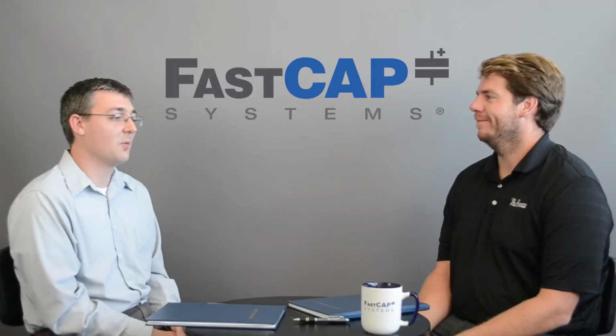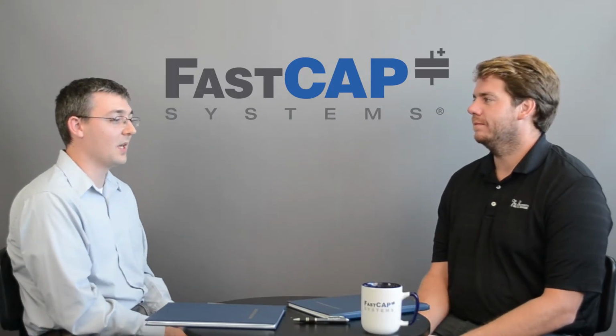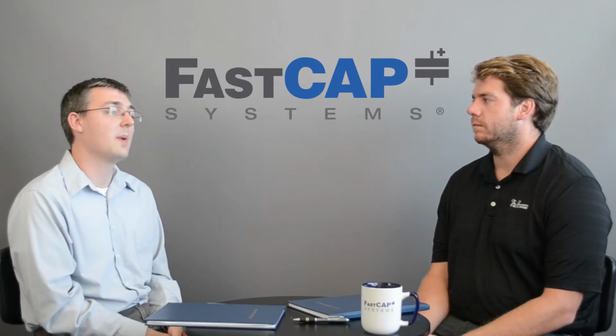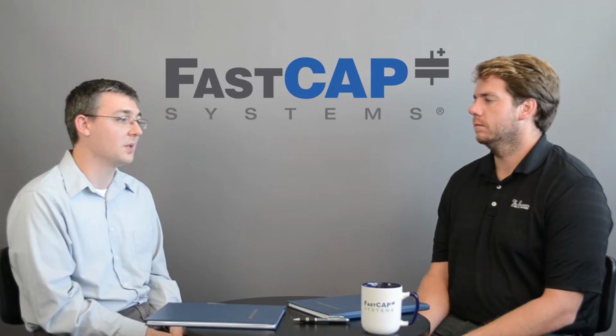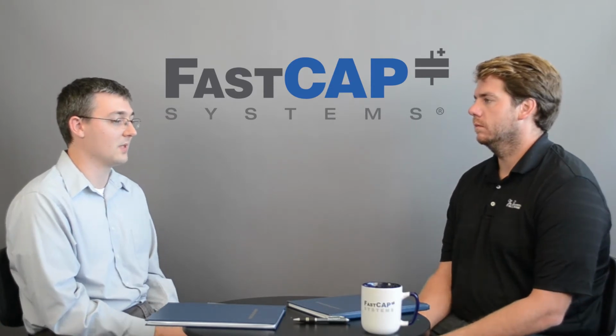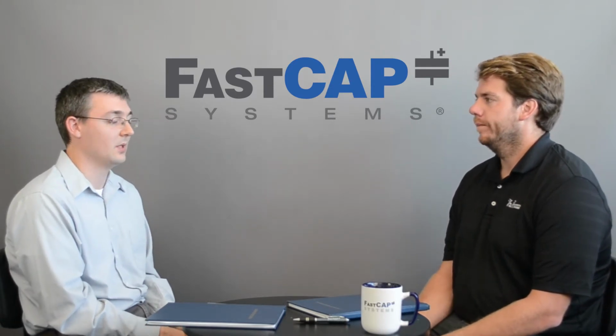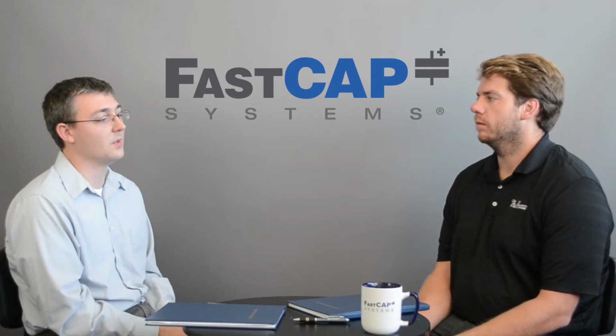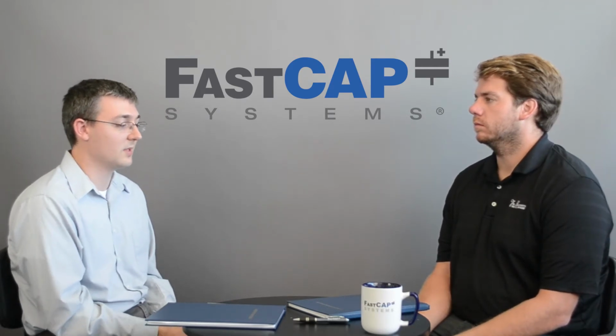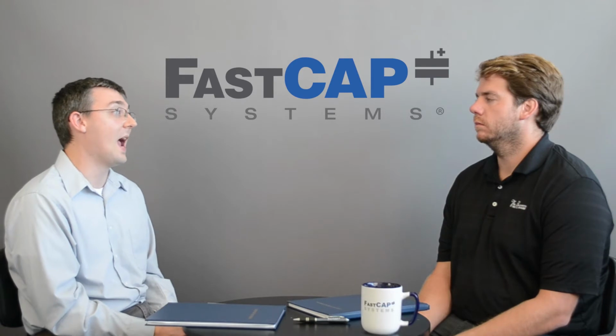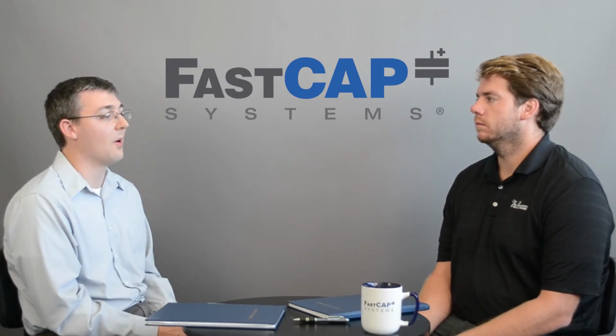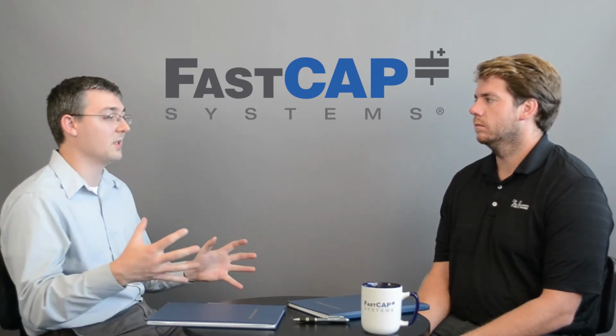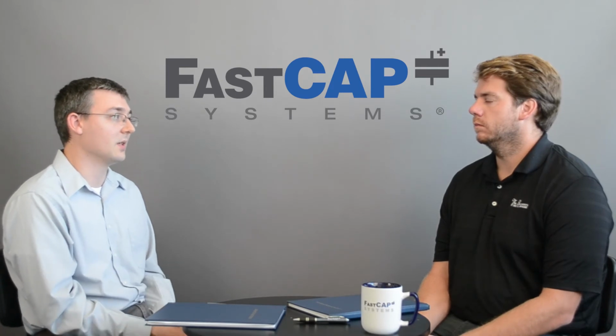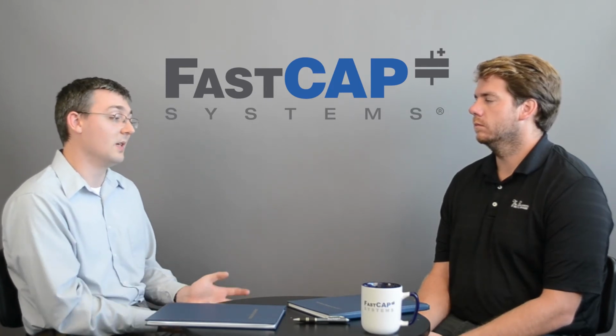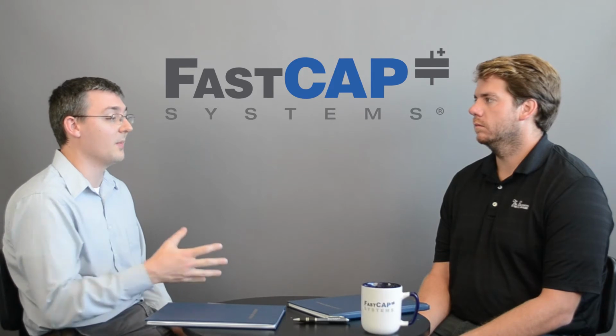The next thing that we look at when considering high power applications is the peak power of the whole system. And peak power is defined as the power at which the voltage on the capacitor stack drops to half voltage. And a lot of times you may not be able to sustain or handle the half voltage mark. So at what power and at what energy, what time duration at that power do you actually need, and then over time, how will that change?